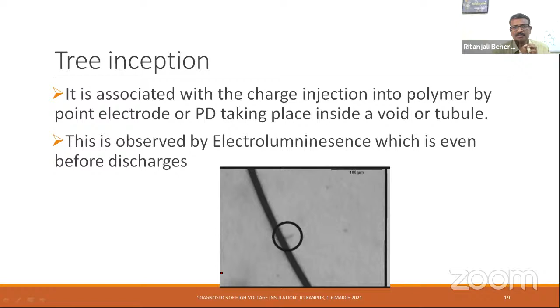Partial discharge in tree: small voids inevitably occur at these points I've mentioned. Since the permittivity of the gas is much less than the permittivity of the polymer, field intensification occurs at the end walls. In other words, the void gets more stress compared to the solid insulation, and hence partial discharge takes place within the void, and this activity is very repetitive.